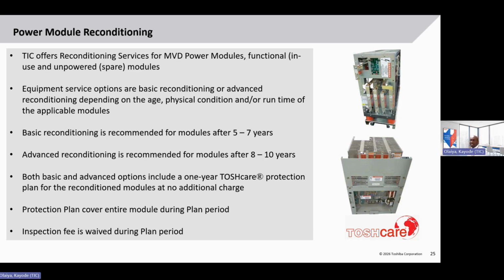We have had countless examples of customers who have had modules for 10 years or more in their warehouse, never used because of the inherent reliability of the Toshiba medium voltage drive. And our experience is most people do not have special warehouses specifically for power modules. The warehouse is usually for everything they have at the site. And so you might have situations where the power modules are not stored in the best conditions. So with the power module reconditioning program, we can help in those situations.